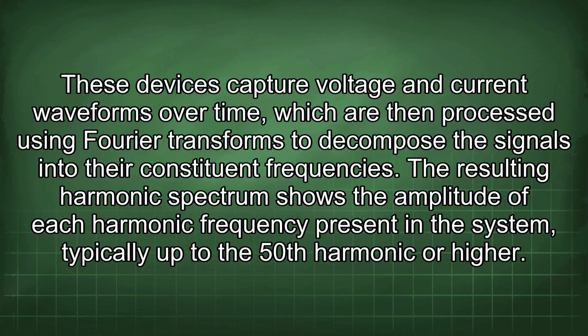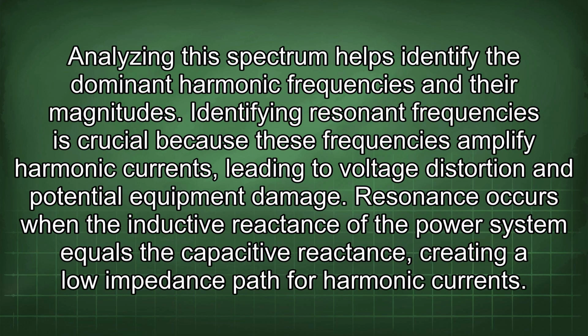These devices capture voltage and current waveforms over time, which are then processed using Fourier transforms to decompose the signals into their constituent frequencies. The resulting harmonic spectrum shows the amplitude of each harmonic frequency present in the system, typically up to the 50th harmonic or higher. Analyzing this spectrum helps identify the dominant harmonic frequencies and their magnitudes. Identifying resonant frequencies is crucial because these frequencies amplify harmonic currents, leading to voltage distortion and potential equipment damage.